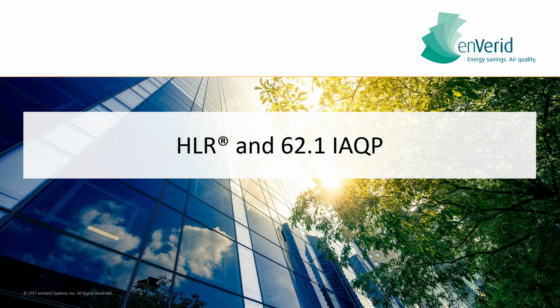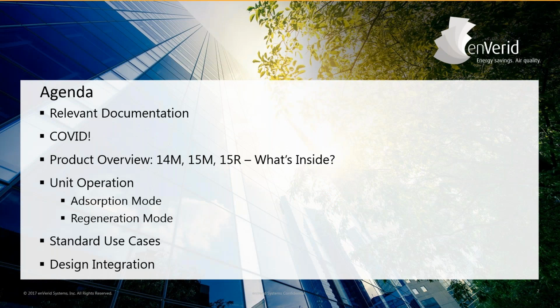We're going to talk about HLRs, HVAC load reduction devices, and the indoor air quality procedure. Basically, what we do at EnVerid is we're not a new company or a new technology, but we basically enable reduced outside air for ventilation purposes by scrubbing the return air as opposed to using outside air to dilute contaminants within spaces. We'll talk a little bit about the product.